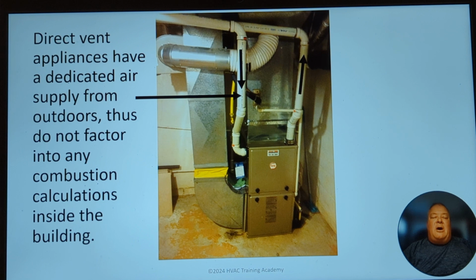Direct vent appliances have their own dedicated air supply systems coming in from outdoors. It isn't always a high efficiency furnace like we have pictured here. It could be a tank style water heater or a tankless water heater. A lot of room heaters now are direct vented, and a lot of fireplaces as well. They bring all the air they require for combustion in from the outside through the snorkel, and the exhaust goes through its own dedicated pathway back outdoors. Because it doesn't take any air out of the building for combustion purposes, we don't have to calculate it in when we're figuring out combustion and ventilation air openings.